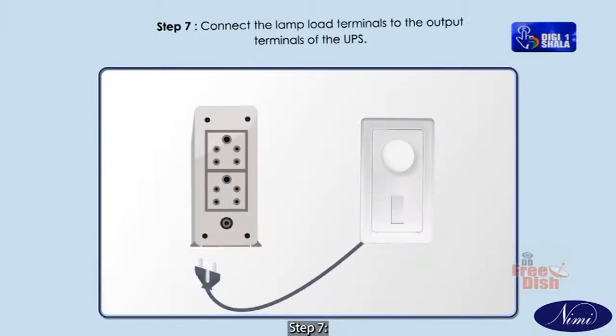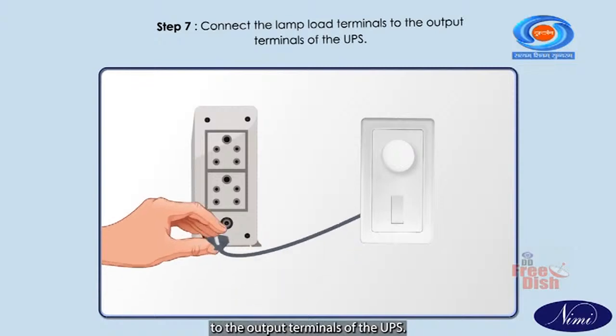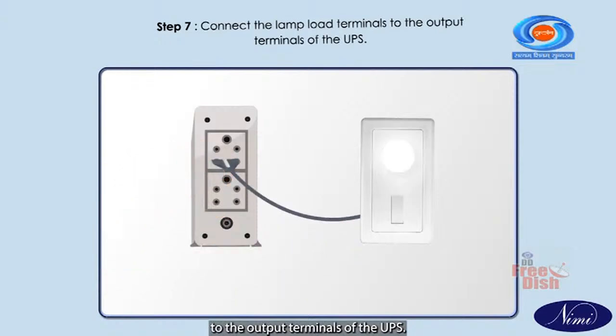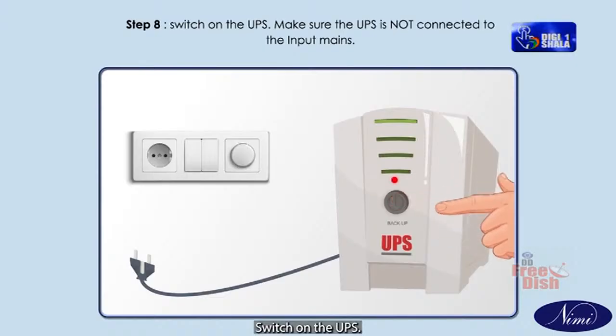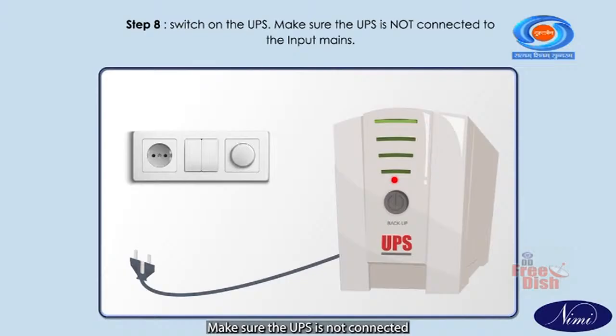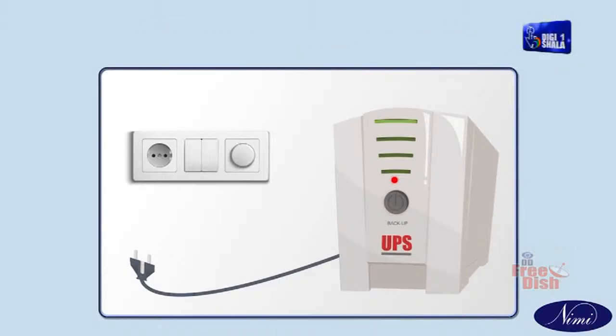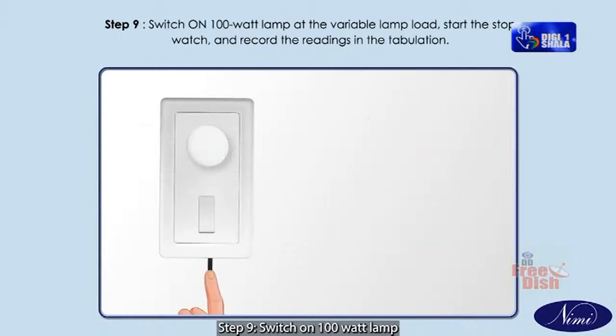Step 7. Connect the lamp load terminals to the output terminals of the UPS. Step 8. Switch on the UPS. Make sure the UPS is not connected to the input mains. Step 9. Switch on the 100-watt lamp at the variable lamp load.